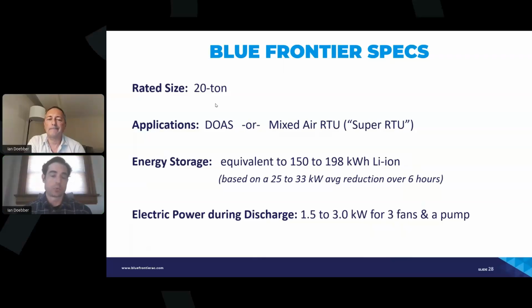We've been calling this the super RTU because the unit is so effective at dehumidification, it can handle much higher outdoor air ratios compared to conventional rooftop units. So for instance, a typical RTU is anywhere from 10 to 25, maybe 30% outdoor air ratio that it can handle and still meet its supply temperature set points. With our unit, we can go up to 100%. So it gives a lot more flexibility for applications.